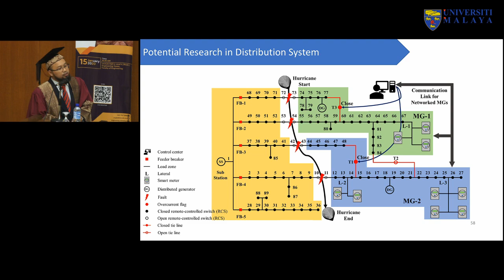We can look at control and stability - different areas can be explored. As I said, when the system is disconnected, the control needs to be changed; it will not be the same as when connected to the grid. It will change totally and this needs to be considered. For example, one of the major problems now is about the inertia of the system, because the penetration of renewable energy nowadays is too high, so the total inertia becomes very low. Small disturbances will cause large problems because inertia helps maintain the frequency of the system. So there's an area called virtual synchronous generator - this can also be explored.